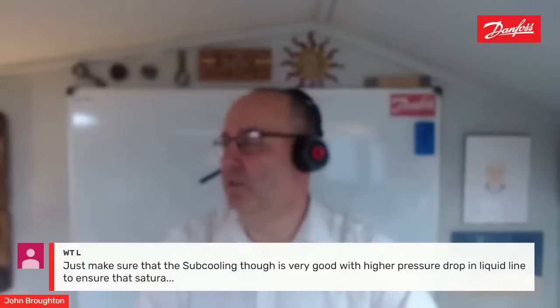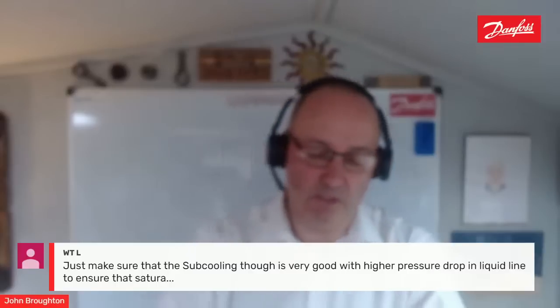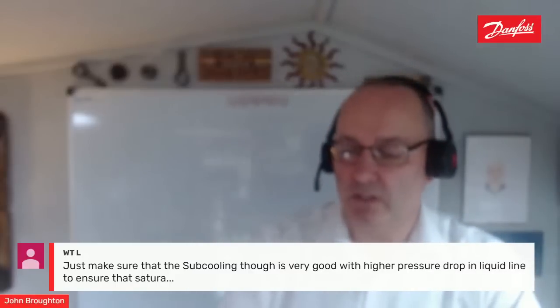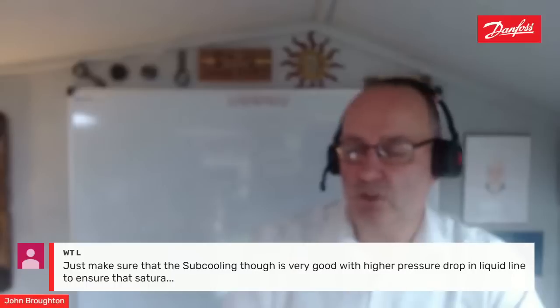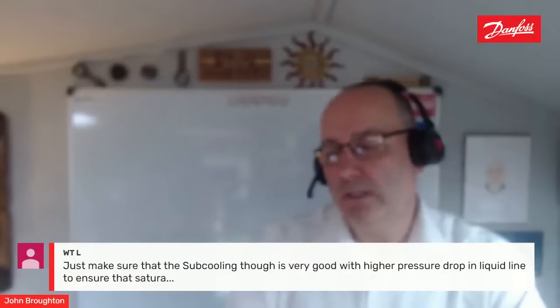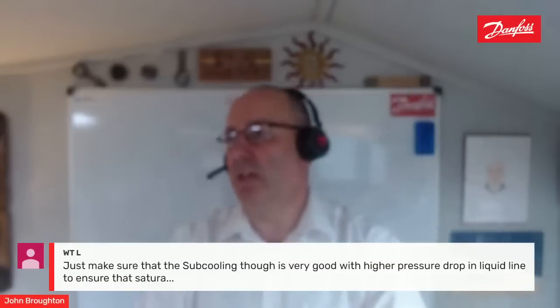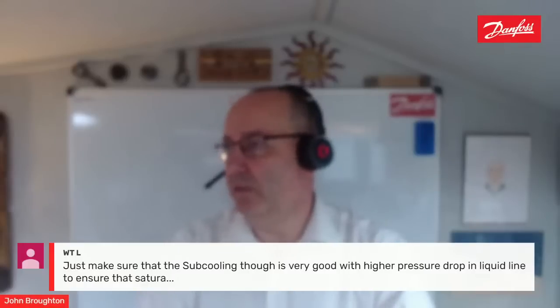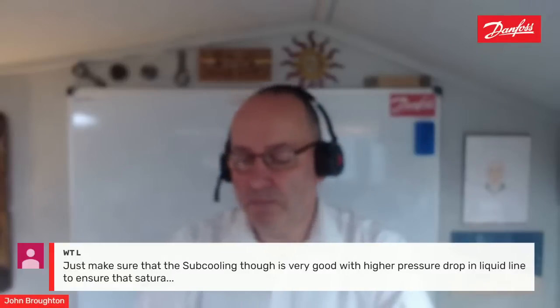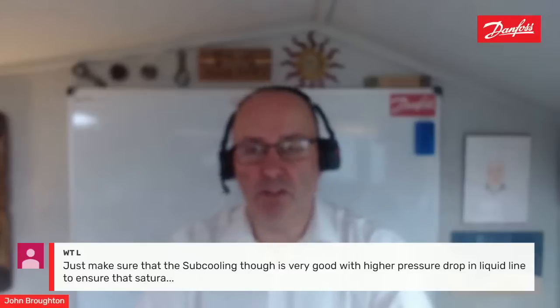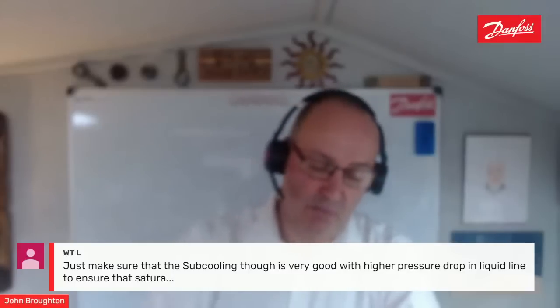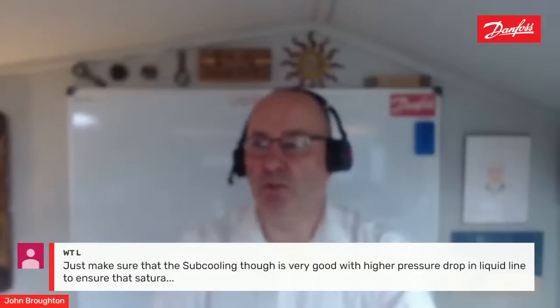expansion. So that's always a good thing to make sure, because as we said regarding the velocity, if you've got too high velocity and your pipe is too small and you've got restrictions, then you can cause flashing, which is never very good for the expansion valve. And generally, if ever people complain about a system not working, at least to me, the first thing that they complain about is the expansion valve.